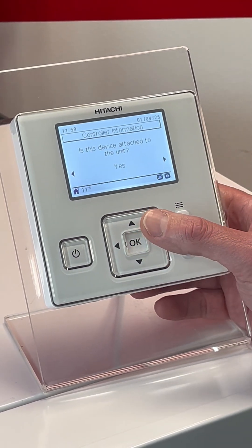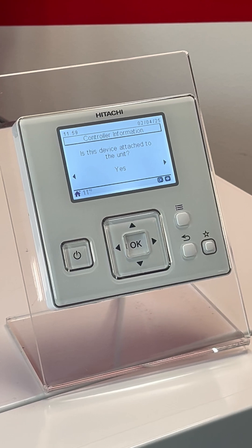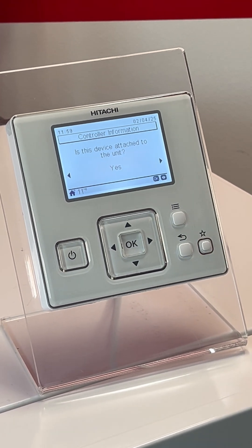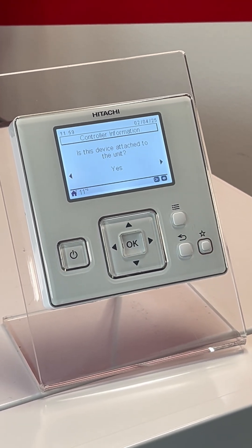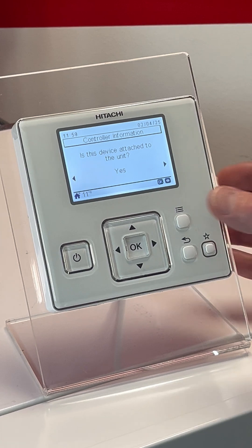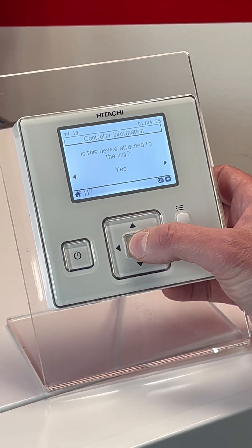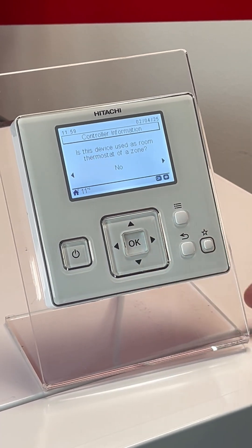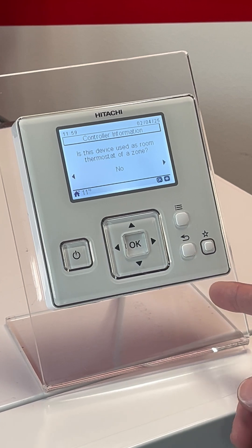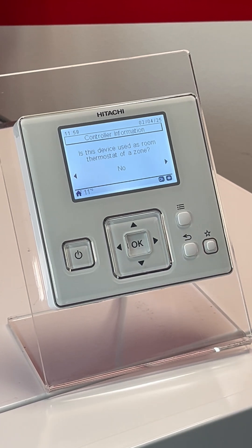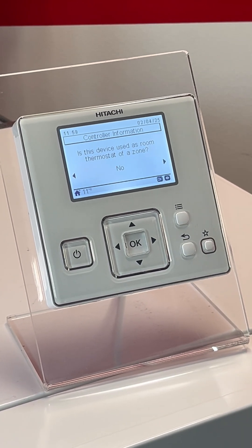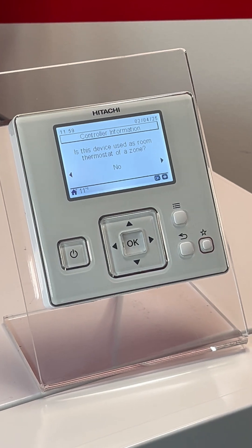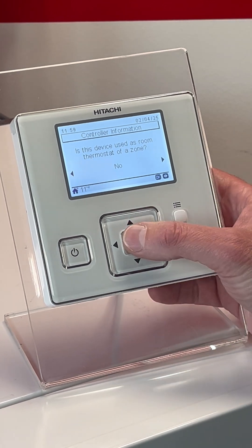Is the device attached to the unit? If it's connected to the heat pump directly, yes. The only time you would select no is if it was being used as a separate room thermostat for a different zone. Is the device used as a room thermostat? This controller has a thermistor in the bottom, so it can be used as a thermostat, but these systems can also be used with third party controls. We're going to say no for the moment.